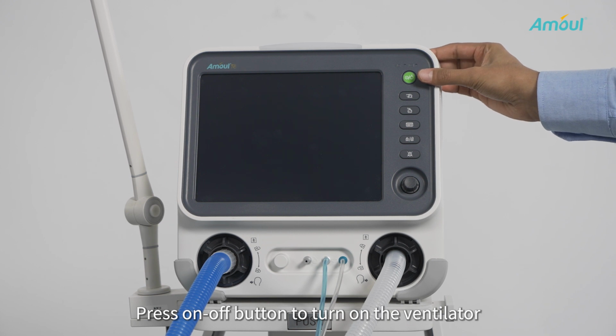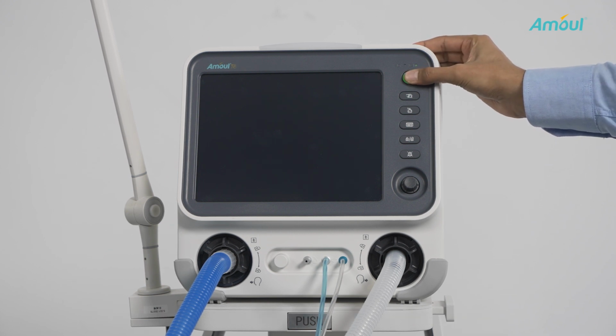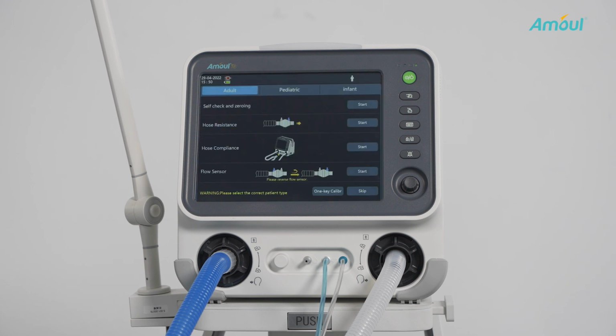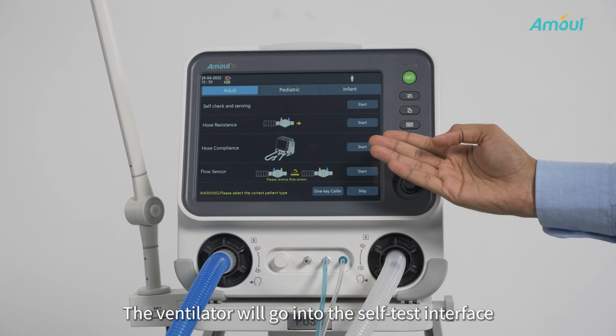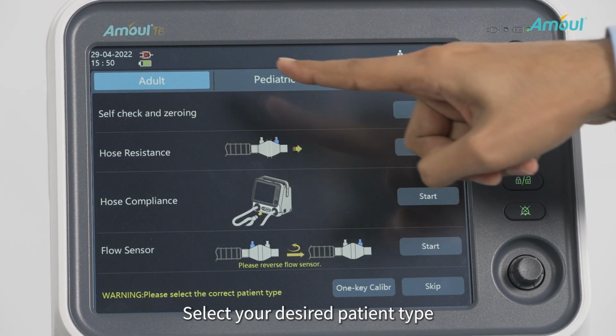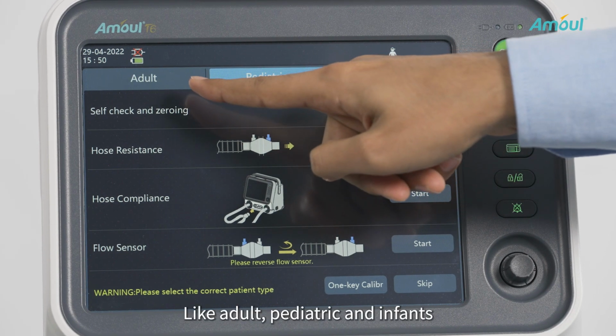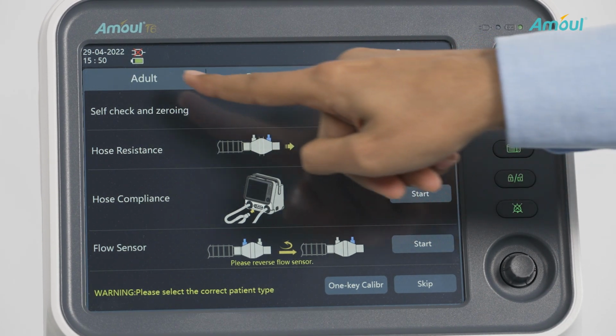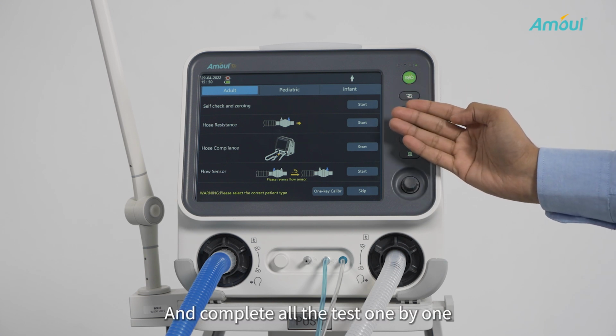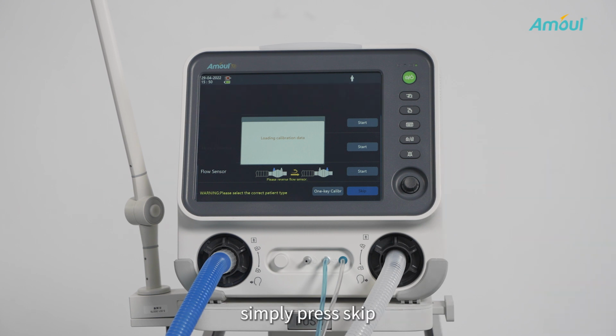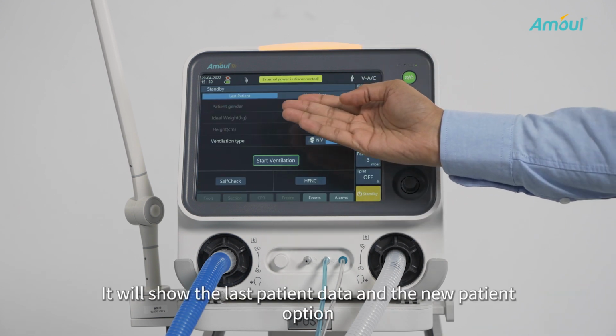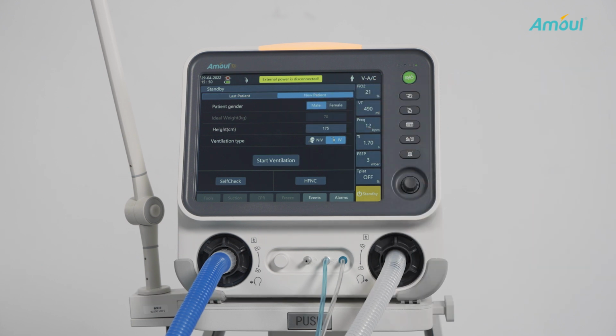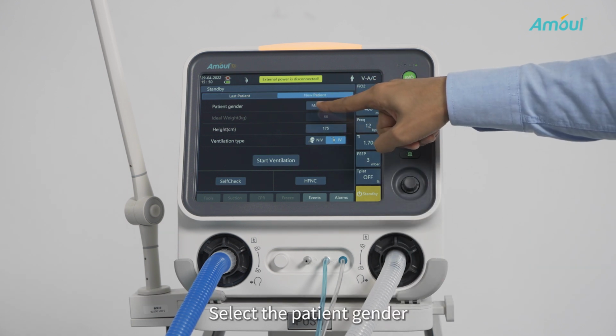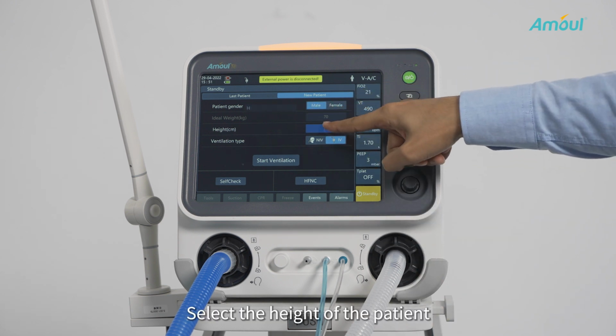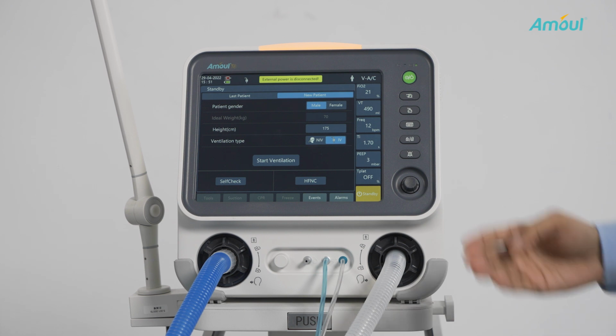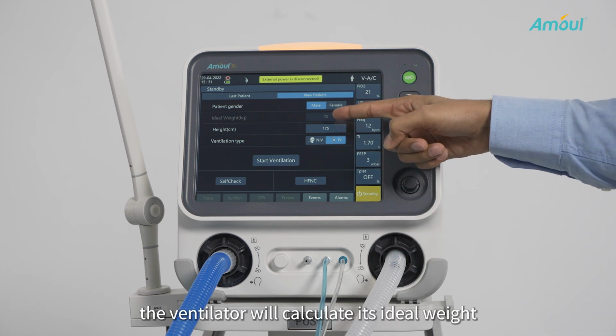Press the on/off button to turn on the ventilator. The ventilator will go into the self-test interface. Select your desired patient type, like adult, pediatric, or infant, and complete all the tests one by one. After completing all these tests, simply press skip. It will show the last patient data and the new patient option. Select the new patient. Select the patient gender. Select the height of the patient. After selecting the height of the patient, the ventilator will calculate the ideal weight.